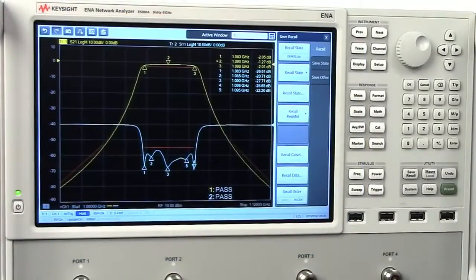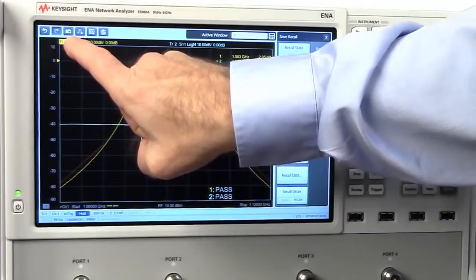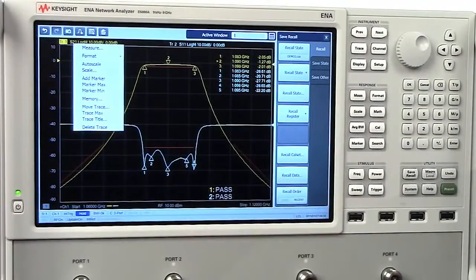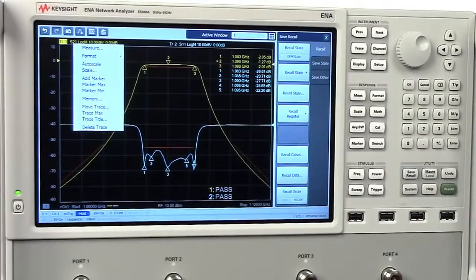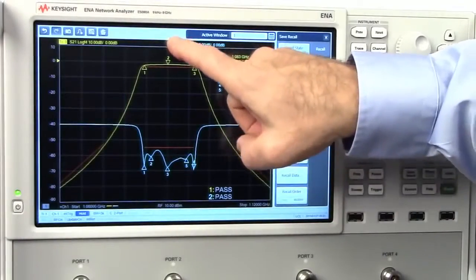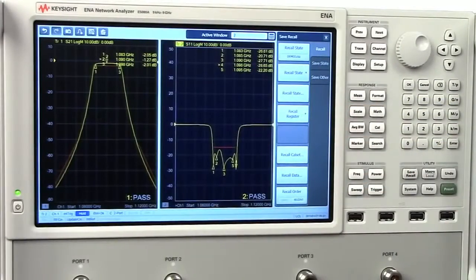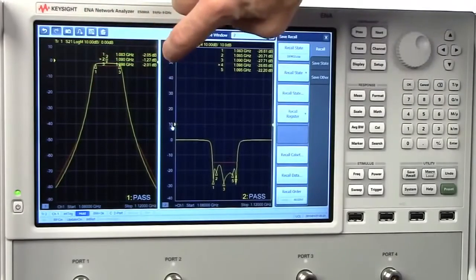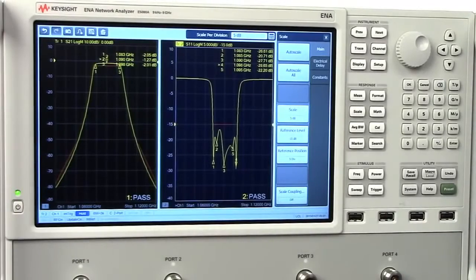On the screen, the new toolbar and an array of context-sensitive pop-up menus provide direct access to essential features, enabling rapid changes to measurement setups. You can change the layout of measurement traces in windows with fingertip drag-and-drop operations. With this touch-based interface, you can also change the reference level and scale and do auto-scale. This new UI will be familiar to existing ENA and PNA users.